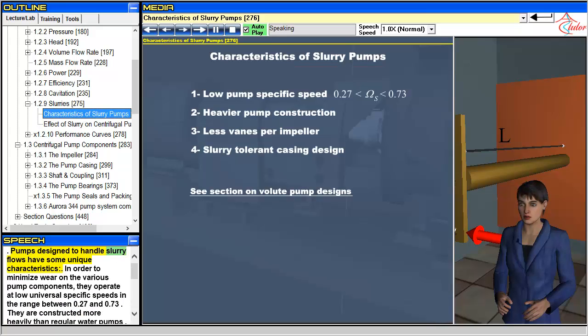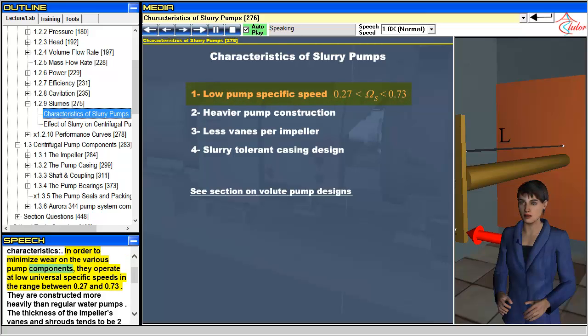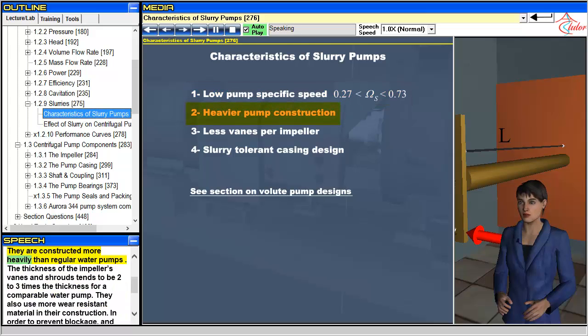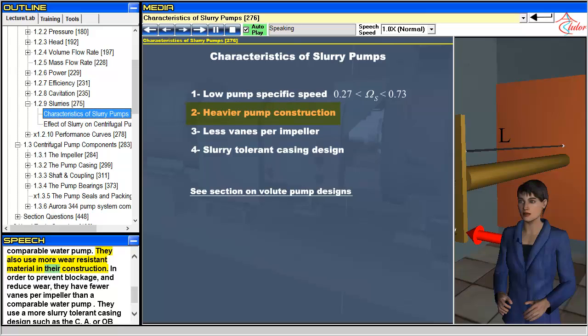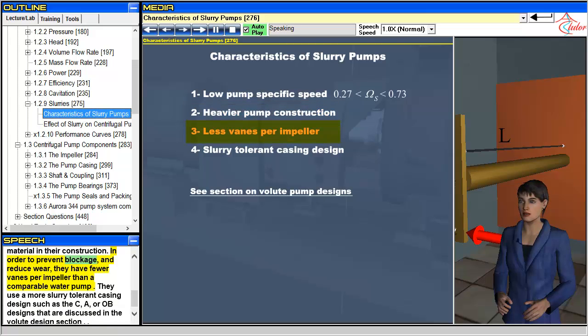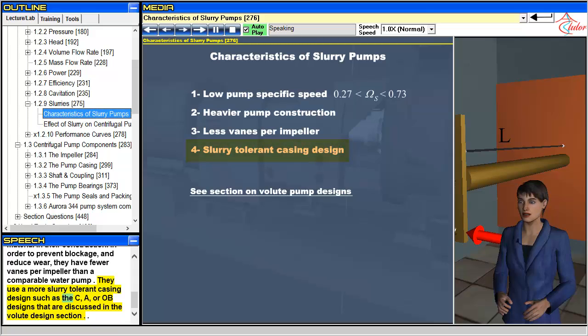Pumps designed to handle slurry flows have some unique characteristics. In order to minimize wear on the various pump components, they operate at low universal specific speeds in the range between 0.27 and 0.73. They are constructed more heavily than regular water pumps. The thickness of the impeller's vanes and shrouds tends to be 2 to 3 times the thickness for a comparable water pump. They also use more wear-resistant material in their construction. In order to prevent blockage and reduce wear, they have fewer vanes per impeller than a comparable water pump. They use a more slurry-tolerant casing design such as the C, A, or OB designs that are discussed in the volute design section.